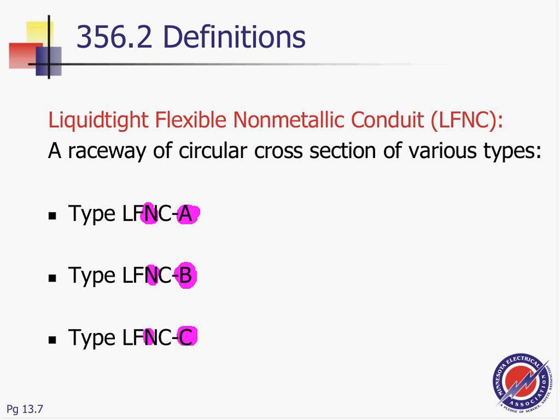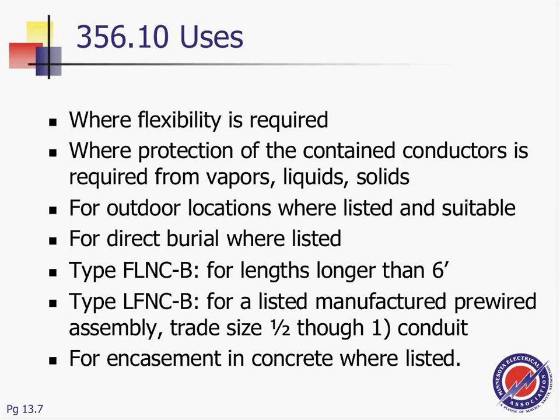Those are the terms of the conduits, as you can read. Let's look directly at where you can use them. For all these conduits, the key point is flexibility. This is not the conduit of choice to wire a house. The main point is flexibility, where protection of the contained conductor is required from some type of solid, liquid, or vapor. They have to be rated for that particular solid, vapor, or liquid. So you need to protect it, especially from liquids, guys. Again, outdoors, this nonmetallic is your conduit of choice. Outdoors, it has to be listed as suitable for the location and for the sun.